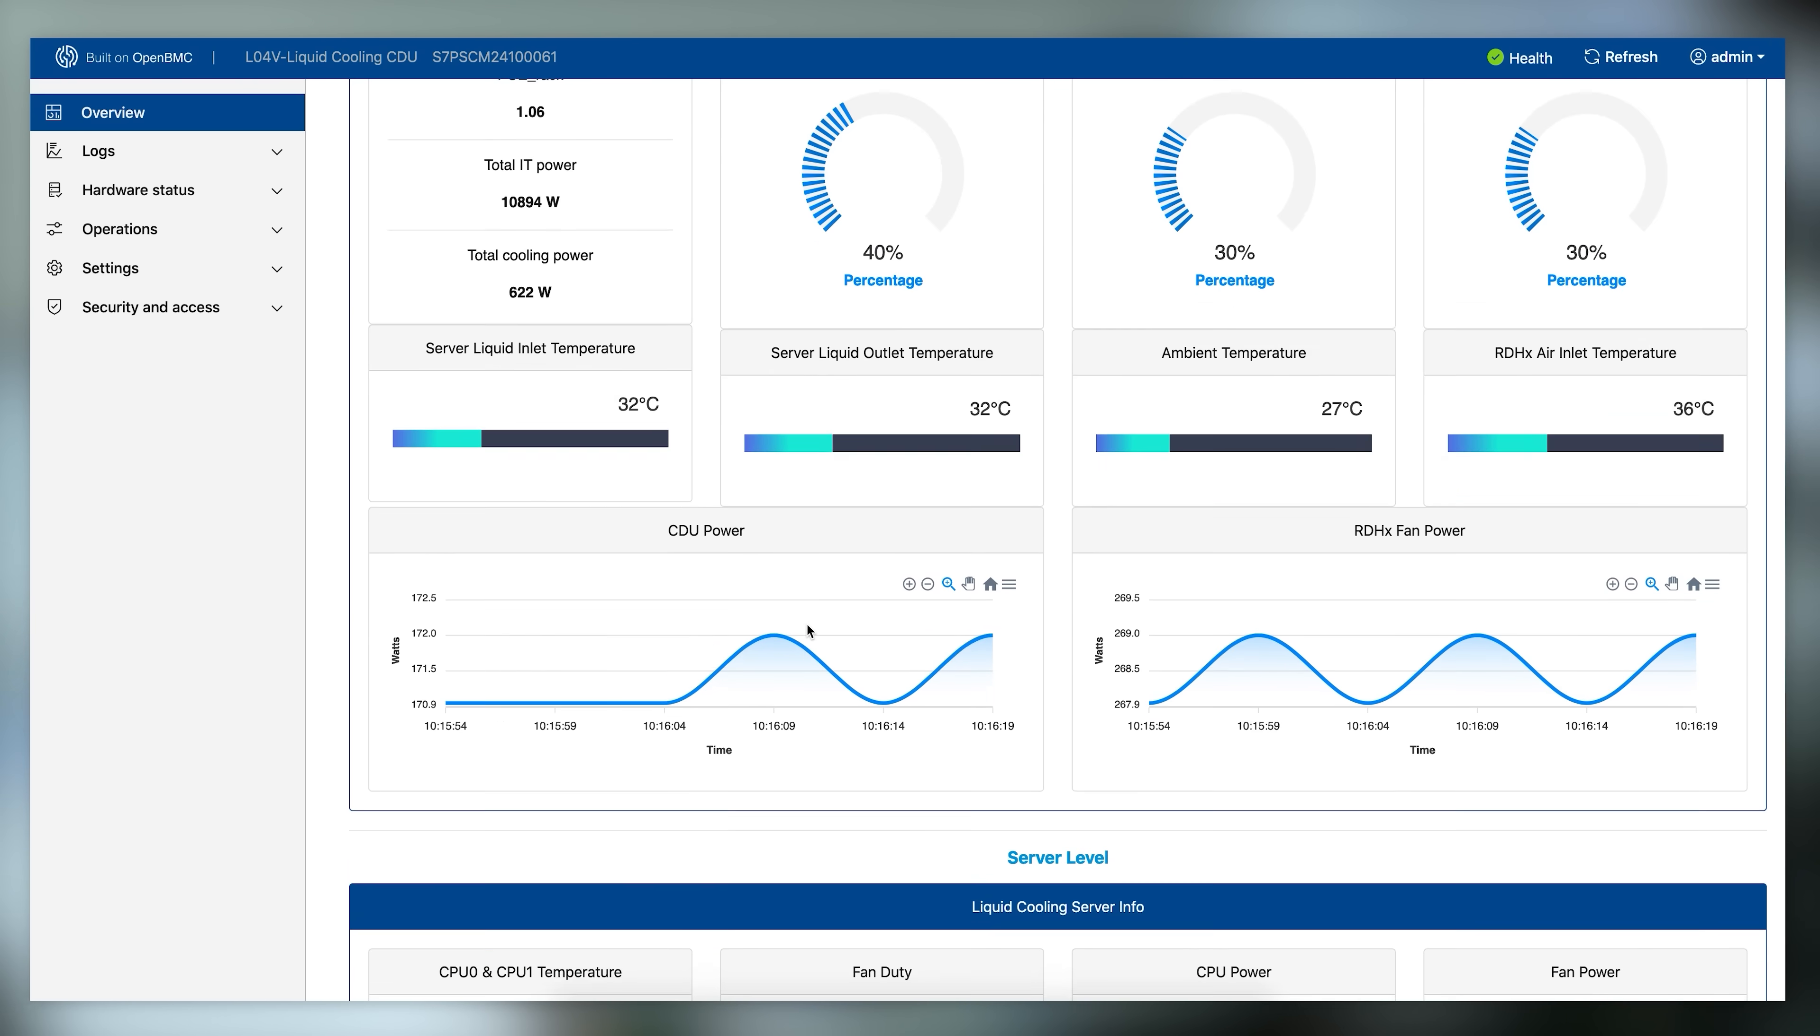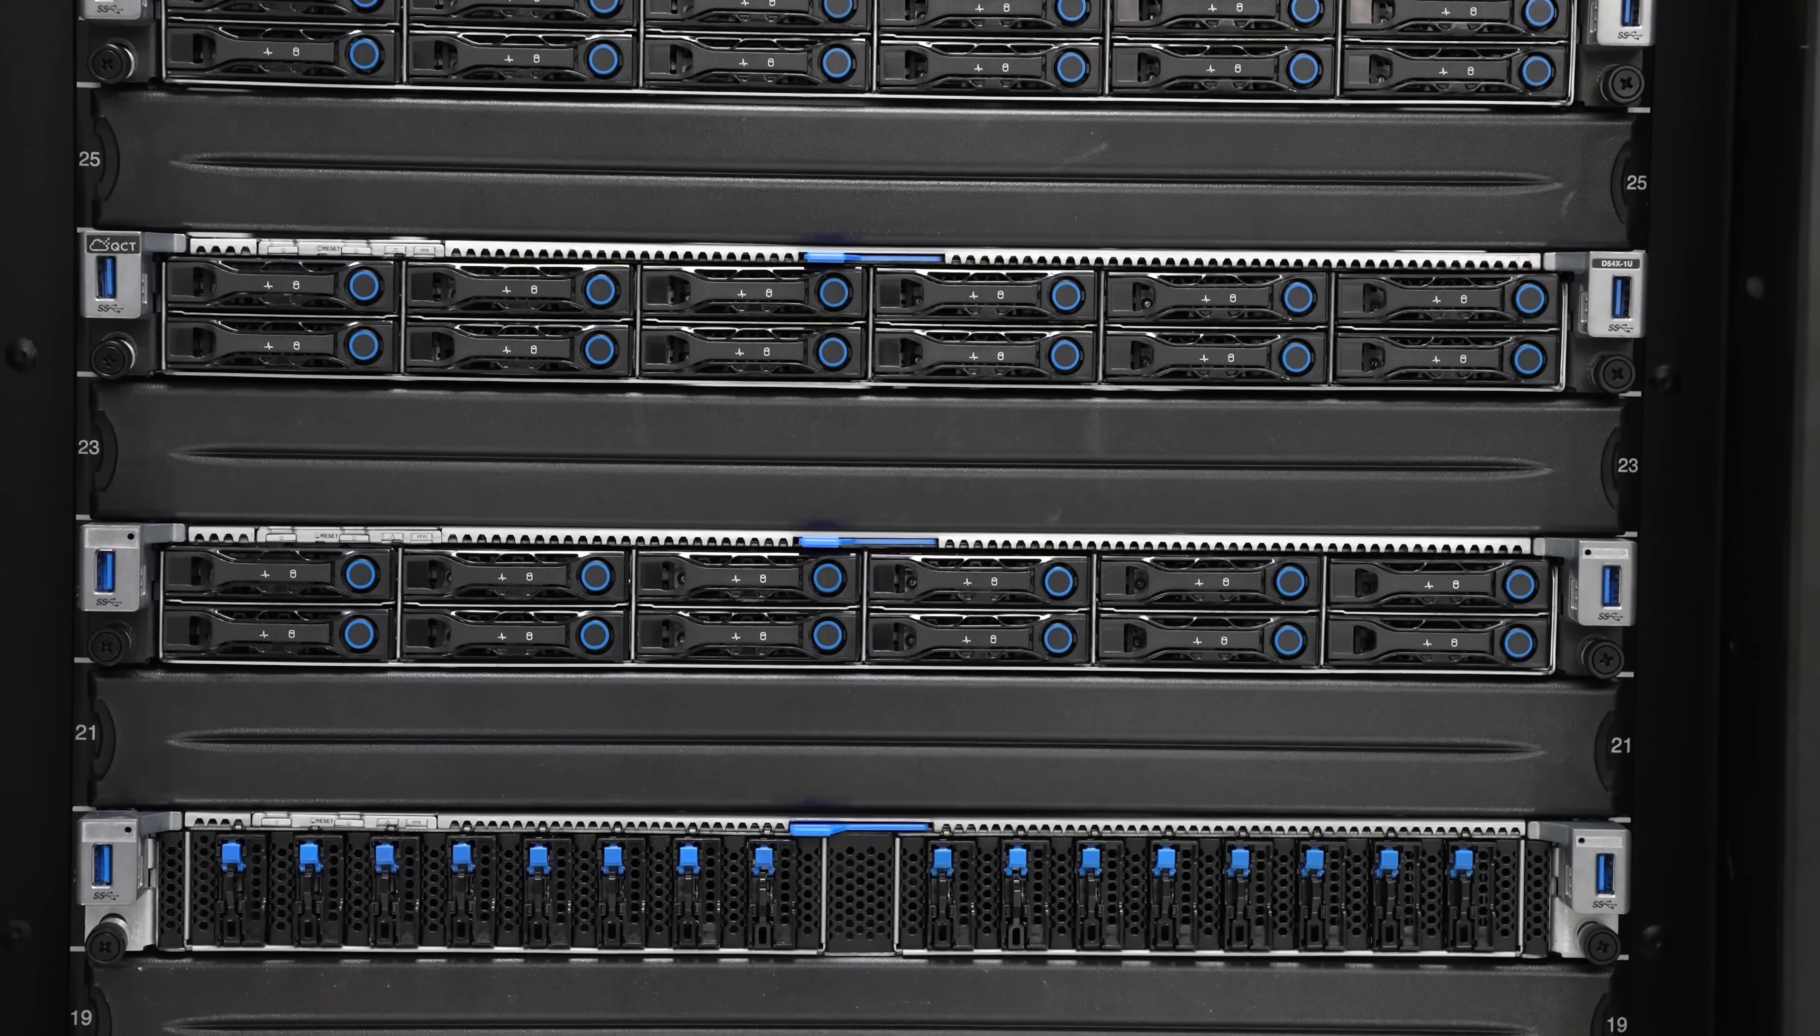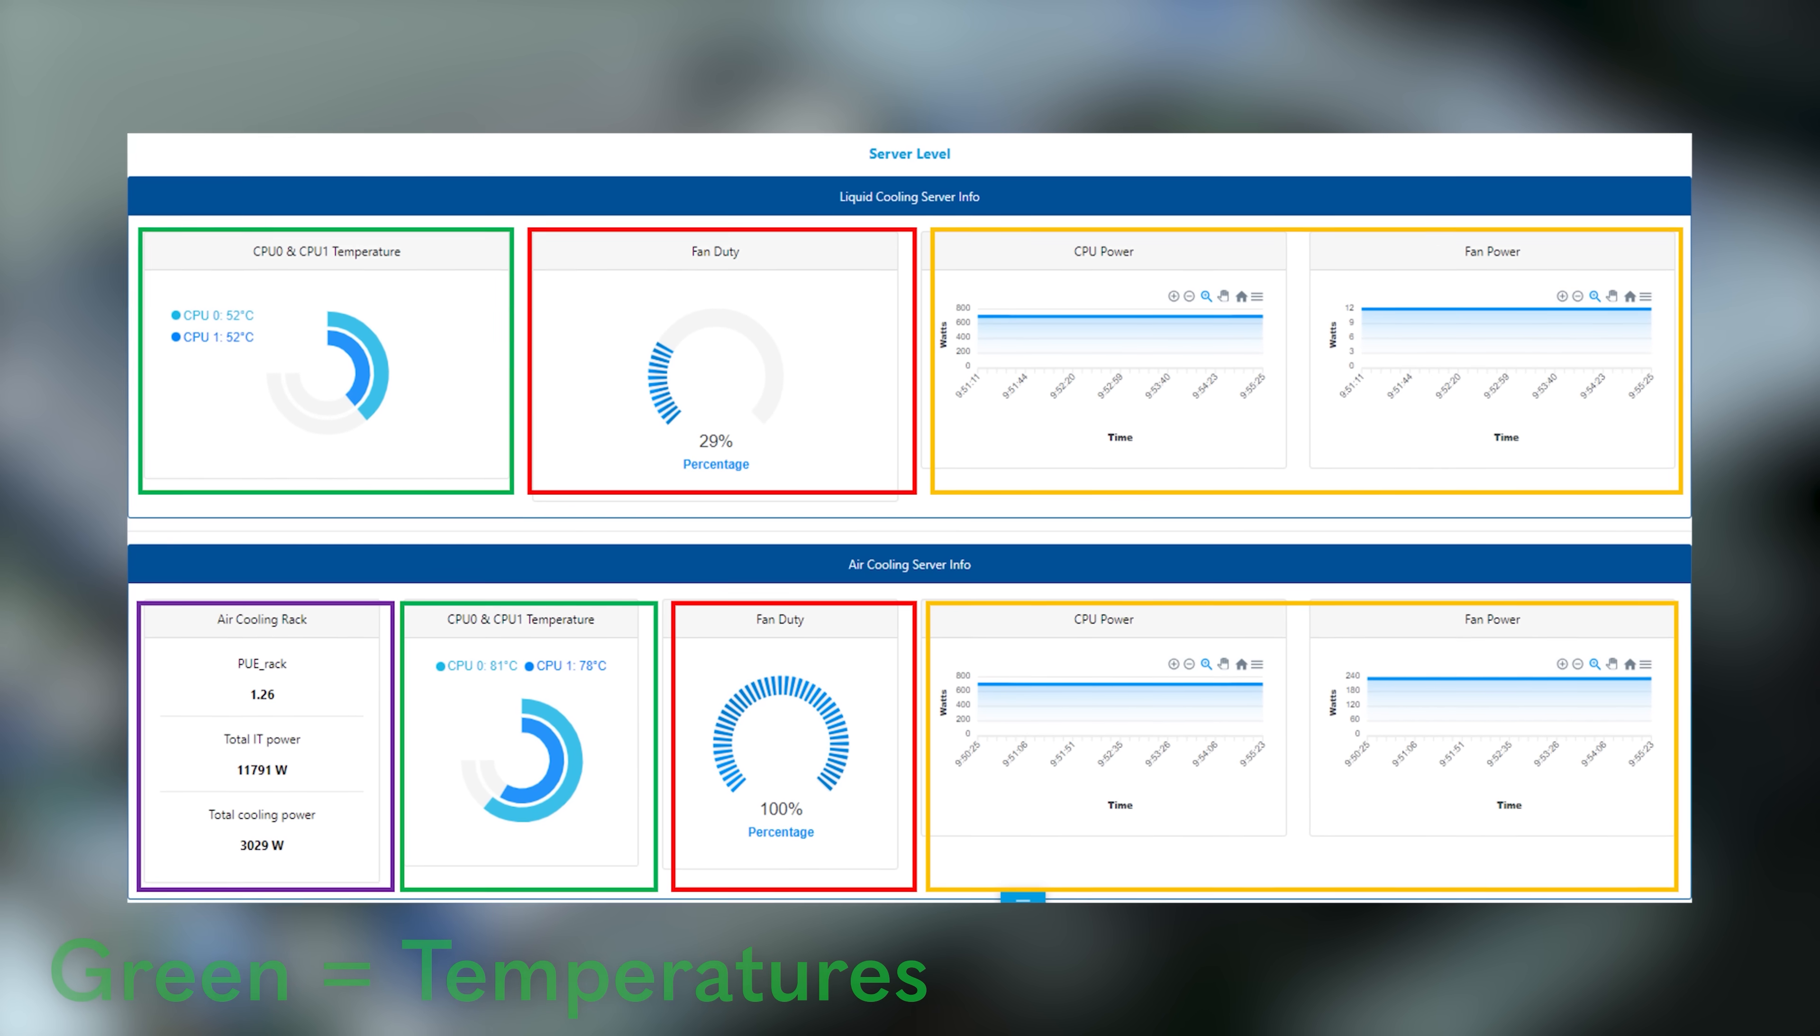Now, of course, QCT has monitoring tools. Now, they have monitoring tools within the server. They also can see, you know, all these modern servers have a bunch of different sensors in them. And then they also have things like monitoring of the CDU so you can see like flow rates and they can see temperatures and all that kind of stuff all throughout the system. So what we did was we not only looked at the ones that we had in the rack with just our little four that we were using for photos, but then we also looked at the full rack scenarios. And something to notice here is just kind of what the difference is between these two racks. So the first thing is clearly the temperatures. If you're looking at the difference in temperature between the liquid-cooled ones, which are in that kind of like low 50 degree Celsius range, and then you compare that to the air-cooled one, which you're like, you know, pushing like 80 degrees Celsius, I think that really shows you the difference between the liquid-cooled and also the air-cooled one.